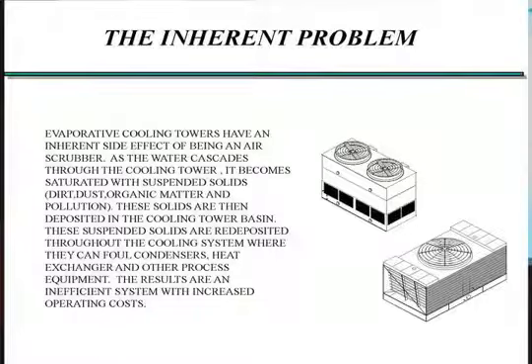Cooling towers are great air washers. Every little piece of junk, and that's a technical term, junk, that's in the air gets washed out into the tower, and the tower essentially collects debris, all sorts of particulates, etc. As you have a cooling tower operating, it's pulling in the outdoor air. That outdoor air brings with it contaminants. The water washes it out, and it gets into your system.